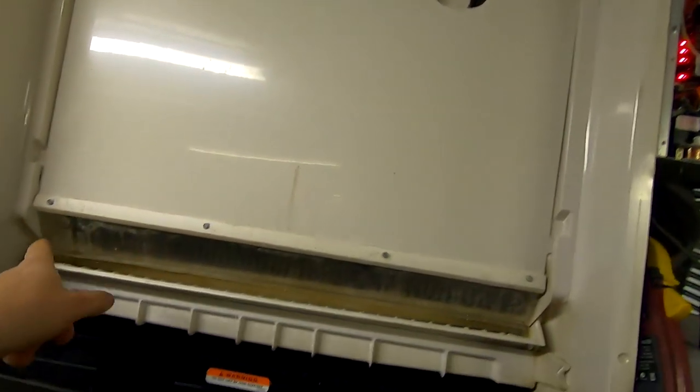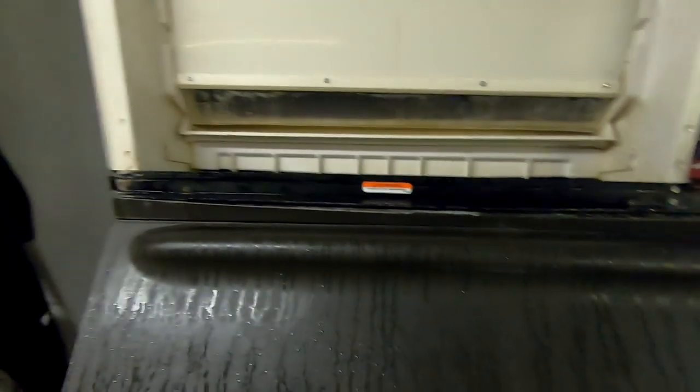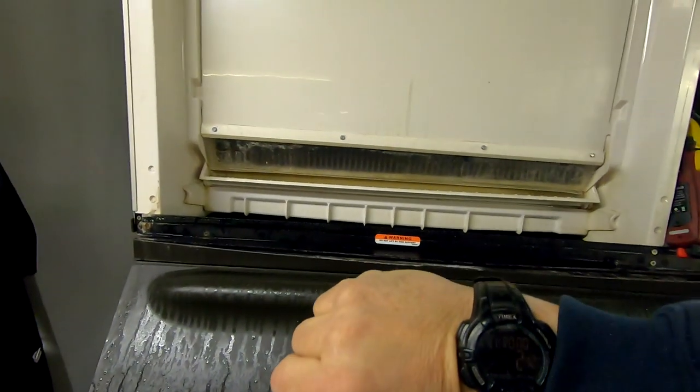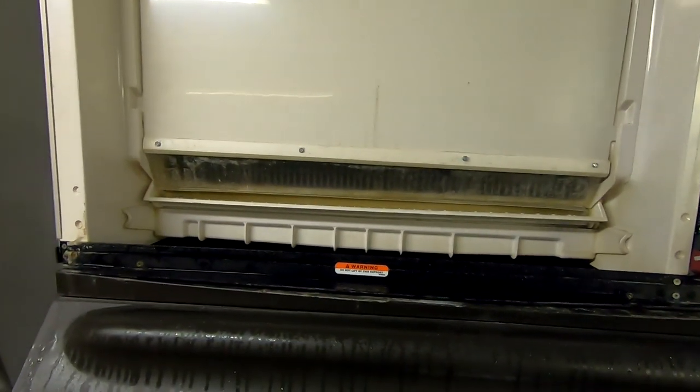This thing makes ice in a hurry. This is a, I think, a 1600. Take a peek at your pattern here. Tell you what, this thing's going to be going into harvest real quick here. So let's watch the frequency here. We're going to start jumping up into the thousands. There it goes.